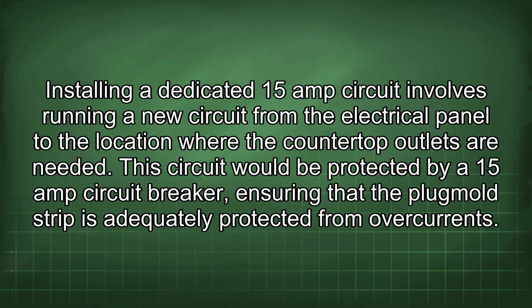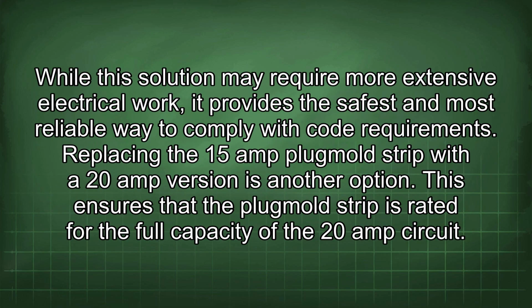Installing a dedicated 15 amp circuit involves running a new circuit from the electrical panel to the location where the countertop outlets are needed. This circuit would be protected by a 15 amp circuit breaker, ensuring that the Plugmold strip is adequately protected from overcurrents. While this solution may require more extensive electrical work, it provides the safest and most reliable way to comply with code requirements. Replacing the 15 amp Plugmold strip with a 20 amp version is another option.